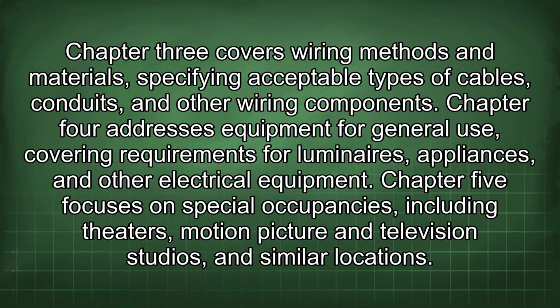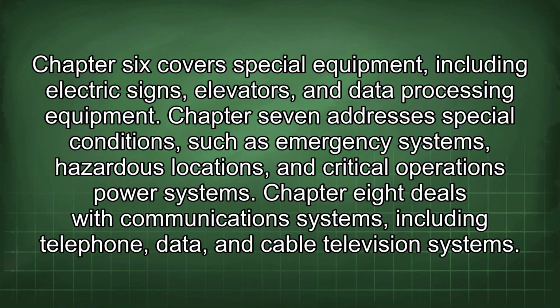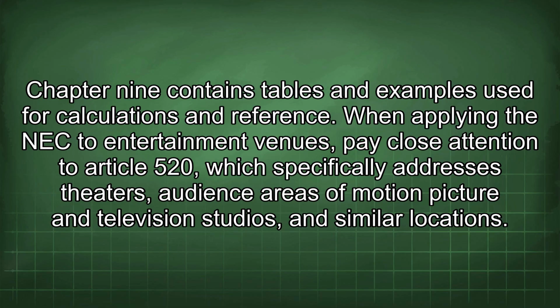Chapter 5 focuses on special occupancies, including theaters, motion picture and television studios, and similar locations. Chapter 6 covers special equipment, including electric signs, elevators, and data processing equipment. Chapter 7 addresses special conditions such as emergency systems, hazardous locations, and critical operations power systems. Chapter 8 deals with communications systems, including telephone, data, and cable television systems. Chapter 9 contains tables and examples used for calculations and reference.